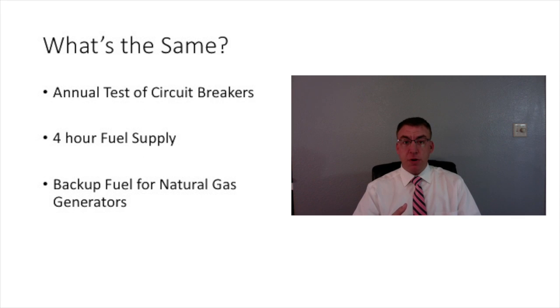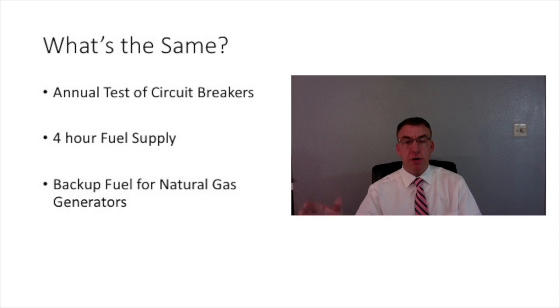Annual test of the circuit breaker. A lot of people have confliction on this. The actual test of the circuit breaker called out in 110 is actually on the circuit breaker. It's between the prime mover generator and the transfer switch. You still have to have a 4-hour fuel supply and backup fuel for natural gas generators.